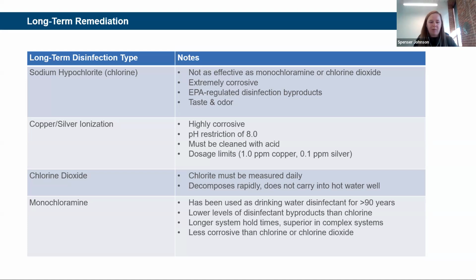And then another option is copper silver ionization. We've seen a lot of facilities start to move away from this. New York State is no longer recommending this as an option. It's highly corrosive. It has a pH restriction of 8, so it can be hard to maintain that always. The plates need to be cleaned on a regular basis with acid. And we found for some facilities that's a problem because they just don't want to have this acid on site to make sure that they're cleaning those. And it has limitations with the dosage limits. So for copper, you have a dosage limit of 1 part per million.